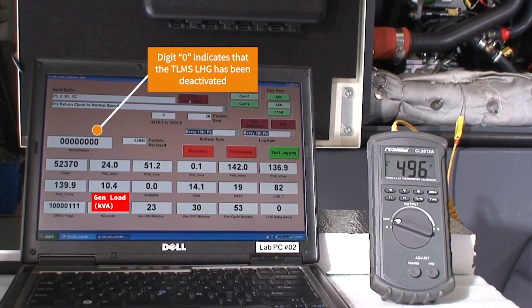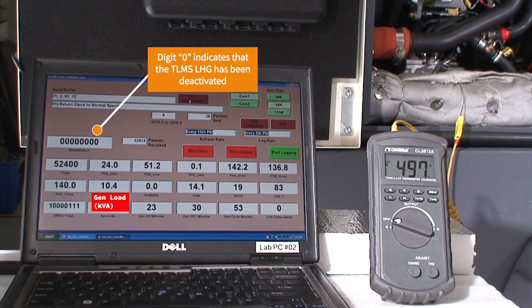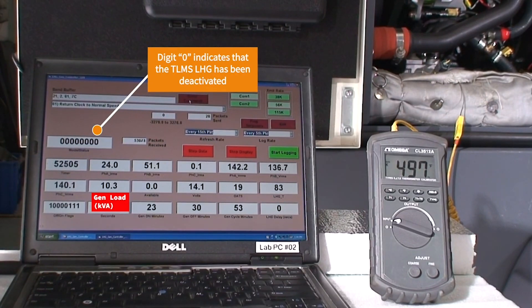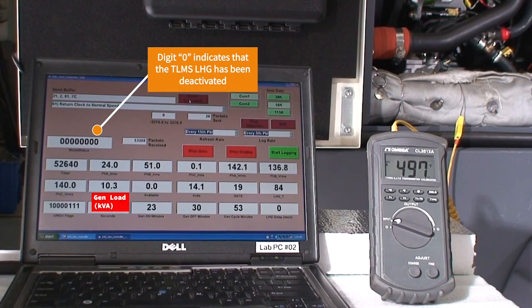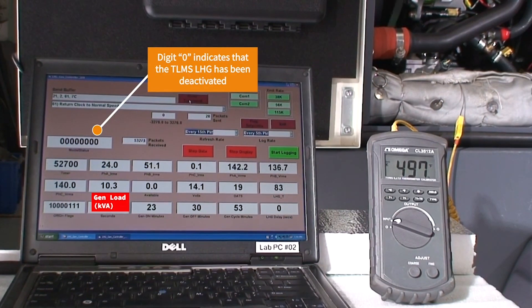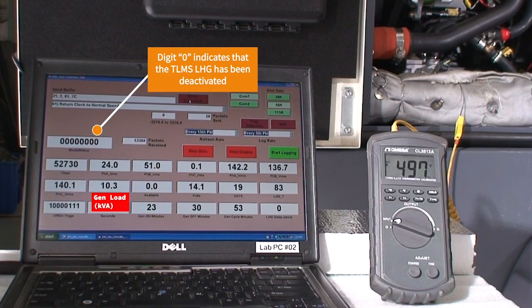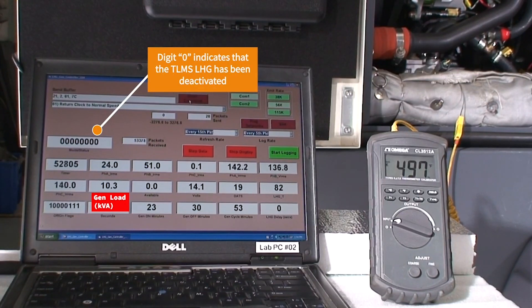Also note that the exhaust gas temperature has not changed. This indicates that the load applied by the load management system is basically the same as the load applied by 10 kilowatts from the load bank.